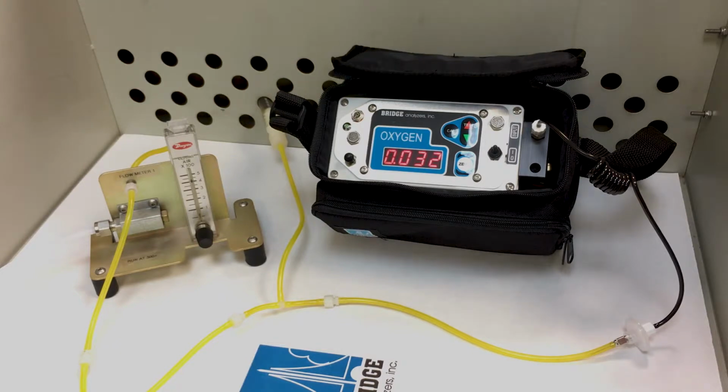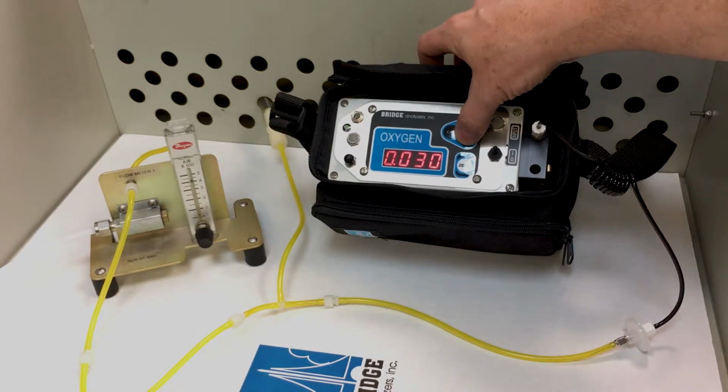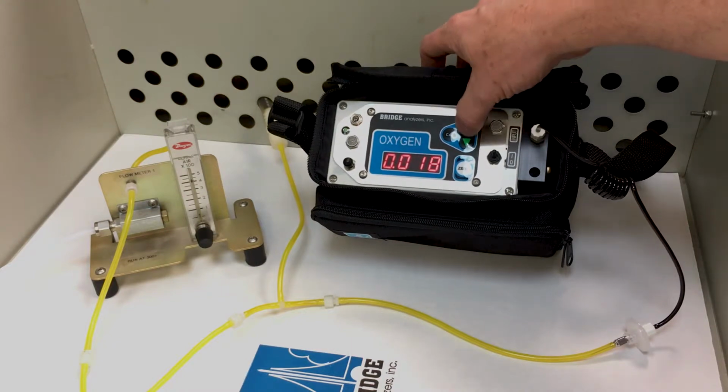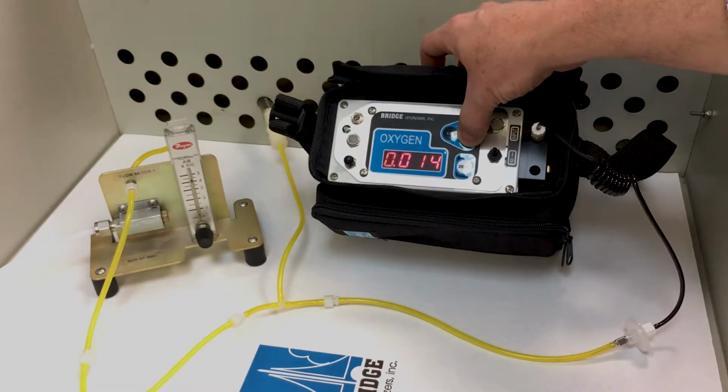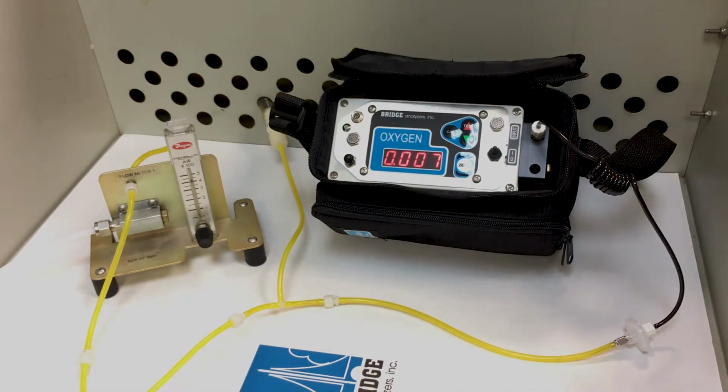So during the time we've been talking, it looks like it's pretty well stable. My oxygen reading is not going down much more. And so now I can say, well, I'm running 0% oxygen. If you think about it, we're actually running right now at 0.03. So this is a very solid reading right out of the box. But if I wanted to, I could hit the down arrow, and that would reduce the bias such that I can lower that value down to something very close to 0.